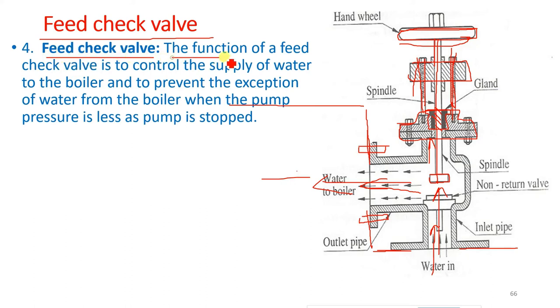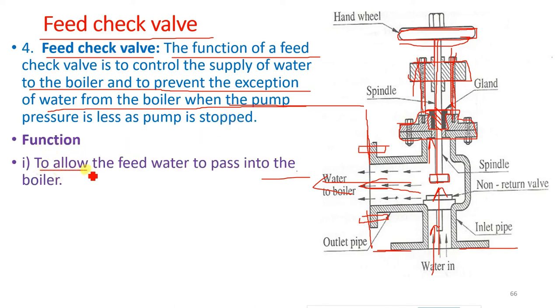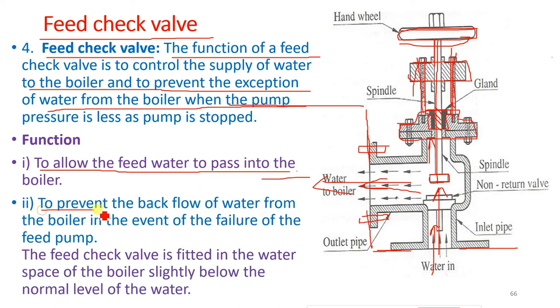Feed check valve: the function of feed check valve is to control the supply of water to the boiler and to prevent the ejection of water from the boiler when the pump pressure is less or pump is stopped. Function: to allow the feed water to pass into the boiler, to prevent the backflow of water from the boiler in the event of failure of the feed pump.